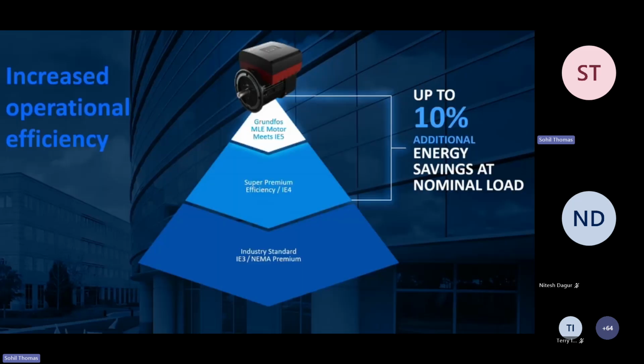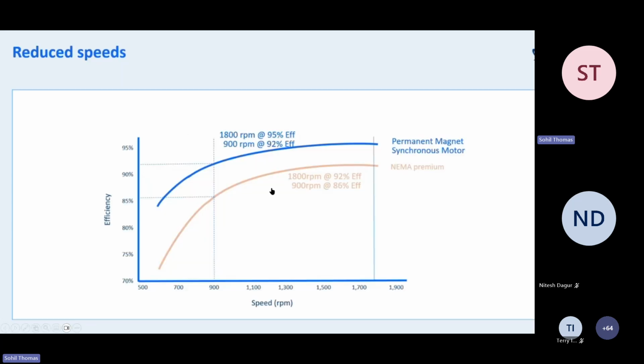With that, we'll go a little bit into the motors we use. In Canada, the minimum requirement on efficiency level is NEMA Premium, which is equivalent to international code IE3. But as you can see, what Grundfos offers is at least 2 levels up, called the Grundfos MLE motor, which gives you IE5 efficiency level, which gives you at least 7 to 10% additional energy savings at nominal load. And if we look at the screen, at full load at 1800 the difference might be a bit less, but you still see that difference here, from 92% to 95%.